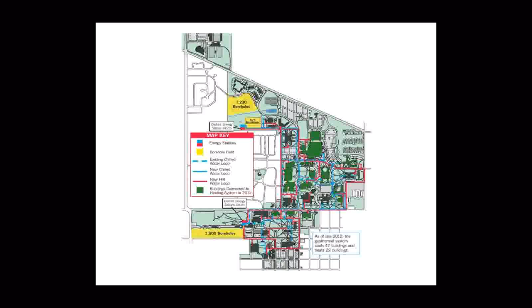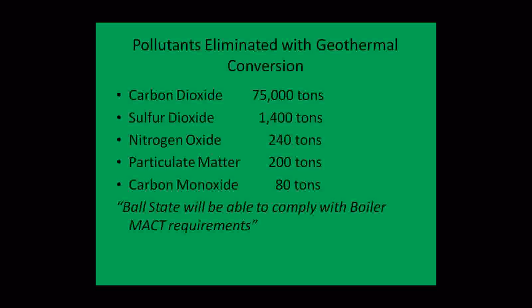We'll nearly reduce our carbon footprint in half with the 75,000 ton reduction. All the emissions issues with coal are gone, and the great thing is Boiler MACT is now, for Ball State, we're in compliance because we're not burning coal, and we will not have to be subjected to adding emission control equipment unless someday the EPA regulates natural gas in some form. The other benefits of the reduction in energy use, it's the COP being 7, will allow us to, number one, not burn coal and buy very little additional electrical power to run our pumps and our heat pump chillers.